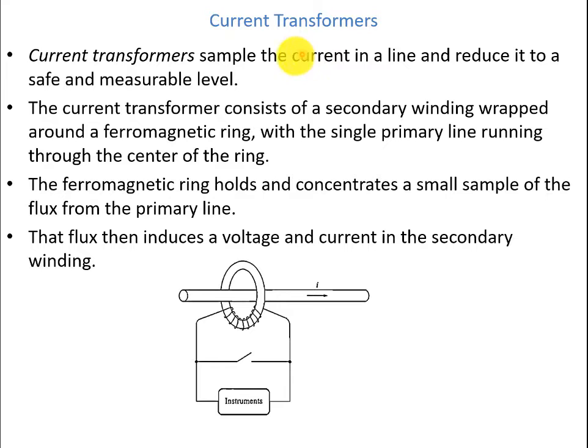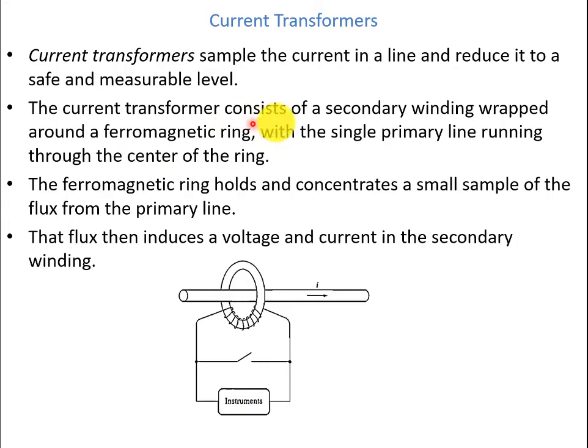Current transformers are transformers that sample the current in a line and reduce it to a safe and measurable level. The current transformer consists of a secondary winding wrapped around a ferromagnetic ring and a single primary line running through the center of the ring. The ferromagnetic ring holds and concentrates a small sample of the flux from the primary line.